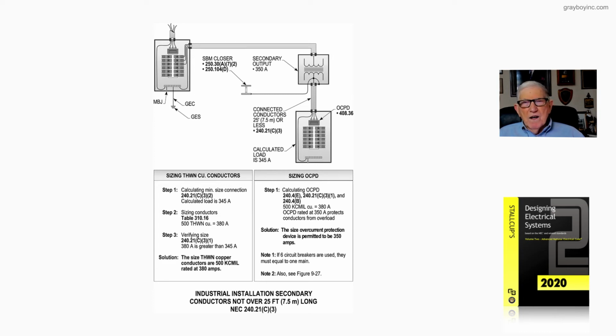Now, sizing the overcurrent device in the next boxed-in set of rules, we look at step 1 for calculating the overcurrent device, and 240.4(E) says yes, that is considered a tap, and you can size your overcurrent device accordingly. And 240.21(C)(3) item 1, as well as 240.4(B) as in boy, 500 kcmil, good for 380 amps. We can round it down to 350, and it's going to protect the conductor and protect the output of the transformer as required by 240.21(C)(3). And that's basically what the solution is telling us. Use the 350 amps and you will protect the output of the transformer plus the conductors.